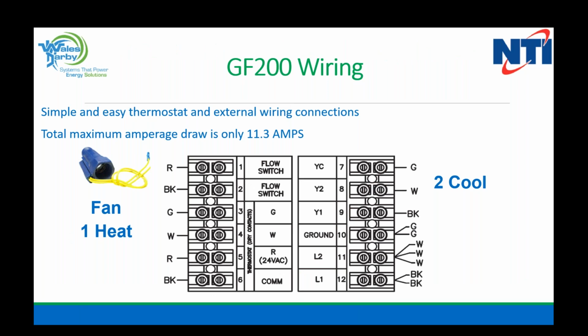From a control standpoint, right on the top left, pretty simple to wire in. You've got your fan, single stage of heat, and your 2 stages of cooling on the right side. Maximum amp draw is 11.3, so we could run a 15 amp circuit. The device you're seeing on the upper left there with the yellow wires, that's the flow switch for the water. It'll wire right in so the unit knows when there's a flow. That goes into the R1 and 2 there, the R and the BK. As water starts to flow through there, it'll report to the controller that there's a hot water demand, and that'll kick the unit on.